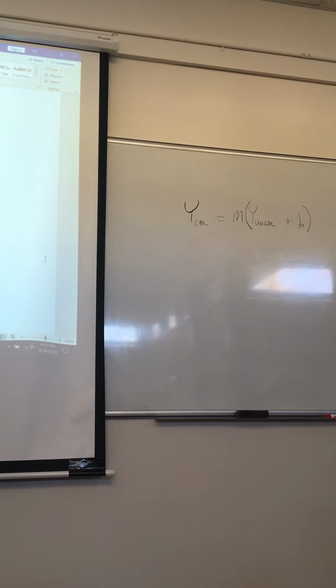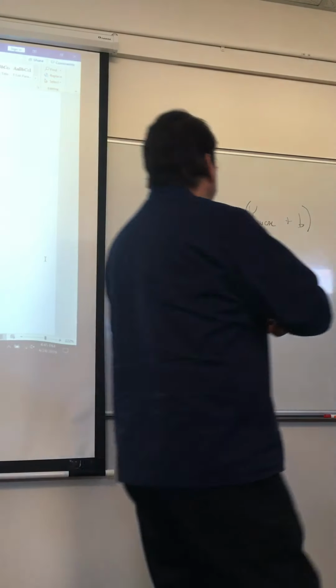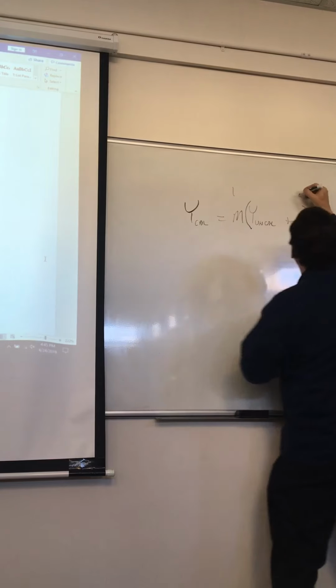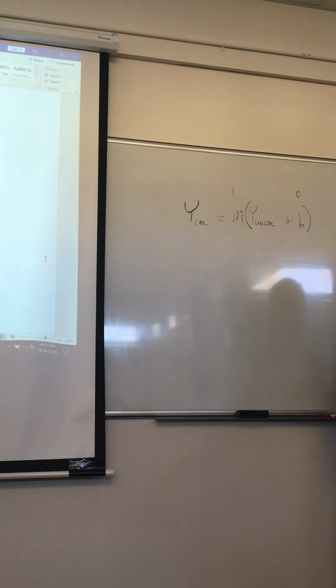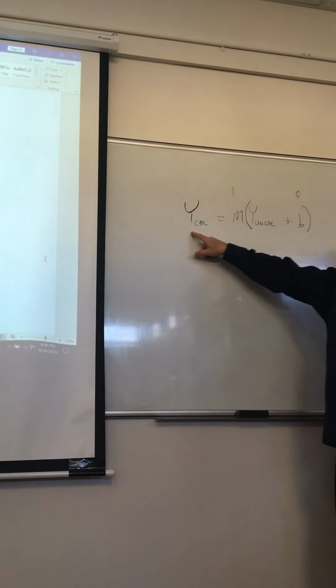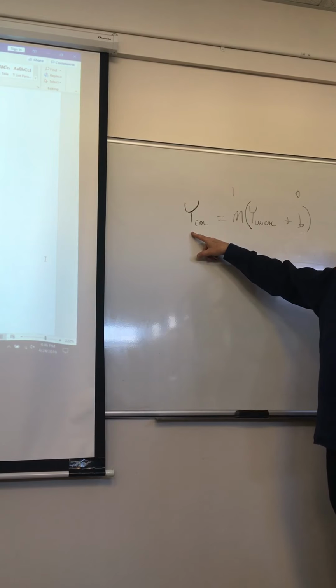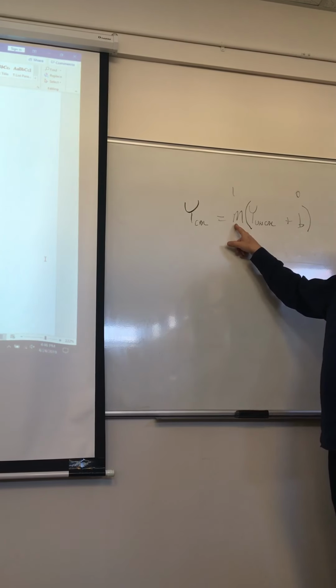And now what does it do? Well, we put M to 1, and we put B to 0. We stick it in ice water and adjust B until this is 0. Then we go stick it in boiling water and adjust M until it gets to be 100. And then we stick it back in ice water, and it should be 0.